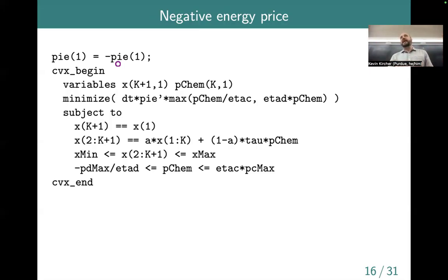So in that case, they might say, look, if wind and other generators in that area continue to produce power, it's going to cause problems on the grid. So we actually want to penalize generation of power. So the price might go negative. And that would send a signal to the wind farm, hey, you should turn off some turbines, curtail some turbines so that you don't get dinged with a penalty. And then the flip side of that on the demand side would say, normally we have to pay for energy that we use, but during these periods, it might actually be the opposite. We might pay you to use energy. And this actually does happen. So in some places in Texas, for example, you can find utilities that soak up wind that would otherwise be curtailed, and they will pay you to use it.